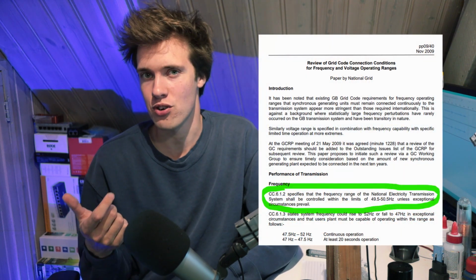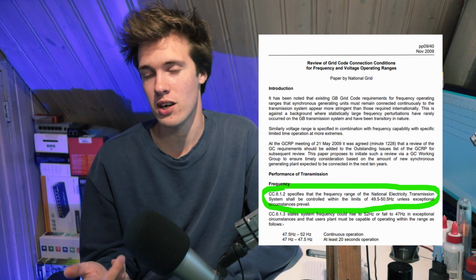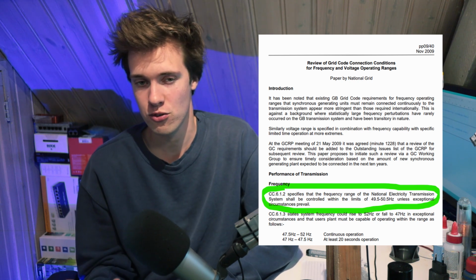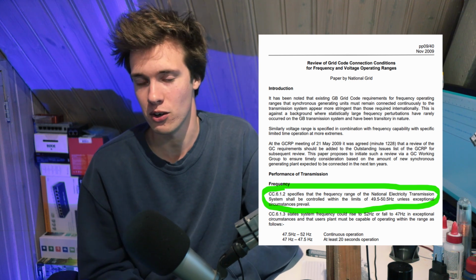Now, something quite important in the world of grid-tied inverters is error detection, particularly when it comes to frequency. The power grid is designed to operate at a very specific frequency - here in Europe, that's 50 Hz. That frequency can vary a little, typically between 49.5 and 50.5 Hz, but the range is quite small. If it goes outside the range of 49 to 51 Hz, there's probably something seriously wrong going on, and power generators and inverters need to shut down as quickly as possible to prevent damage.